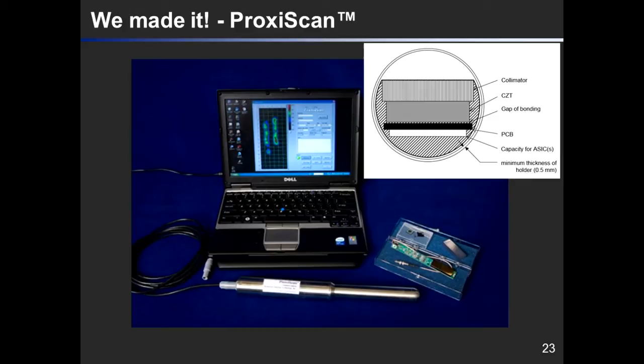This is the imaging probe we made. We package the detector modules into the probe at the very tip. The detector is about here. And here is a handle with the power supplies inside. This computer is used for the image acquisition. If you cut this end and see the cross section, you will see something like this. This is the collimator we mentioned before, and this is the CZT detectors. Here is the printed circuit board from the last slides, and here is a cavity in the shielding to make room for the ASIC. Around all these components, we have the shielding. It's tungsten-based shielding. So it's a very complicated design, especially the shielding.